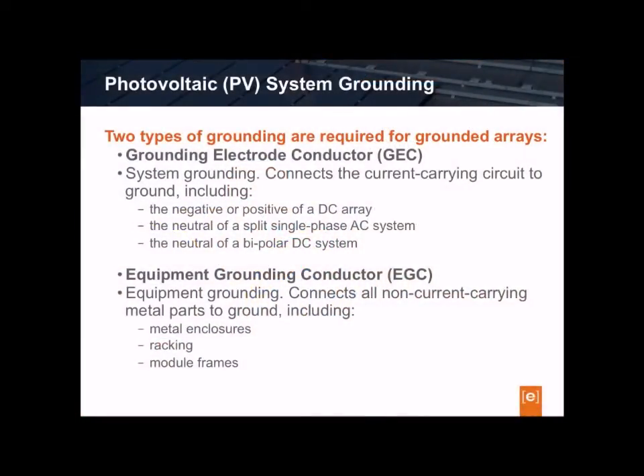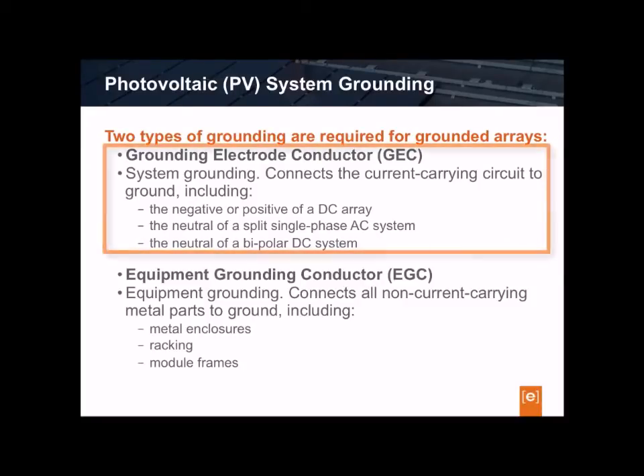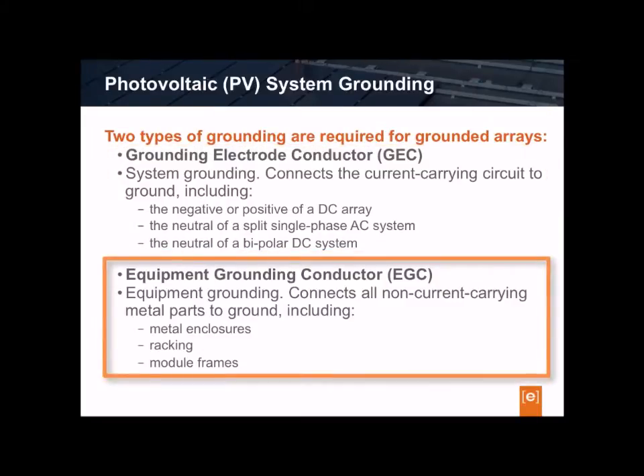Generally speaking, grounded photovoltaic or PV systems have two distinct grounding requirements. The current carrying circuit needs to be grounded with a grounding electrode conductor or GEC — these could include the negative or positive of a DC array, the neutral of a single-phase AC system, or even the neutral of a bipolar DC system. Also, the non-current carrying components of the equipment, such as the module frames, racking, and other metal enclosures, require an Equipment Grounding Conductor, or EGC.